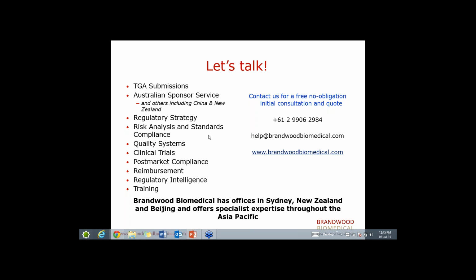There's a question on what international regulatory certifications Australian companies recognize. So as I mentioned, it's pretty much Europe. So CE certification. They don't recognize FDA approvals, but it's one of the key differences with New Zealand. And basically, no other jurisdictions apart from Europe. For some IVDs, they may accept Canadian licenses, but again, it's a complex area, and it's usually on a case-by-case basis. But the simple answer for that is European certification.